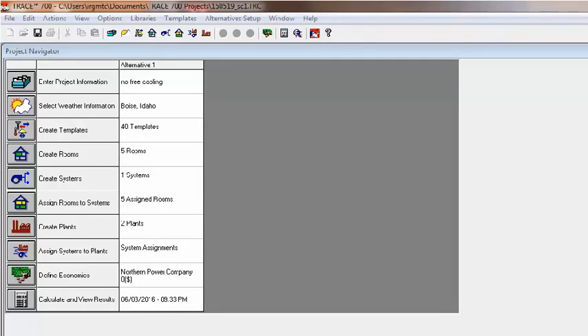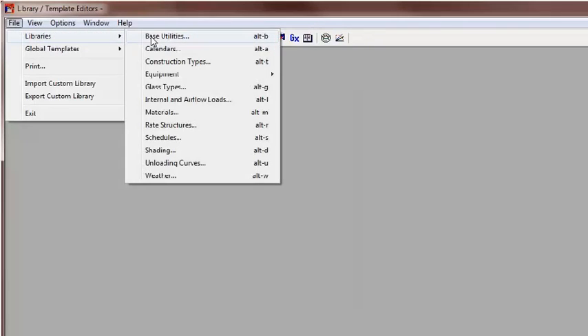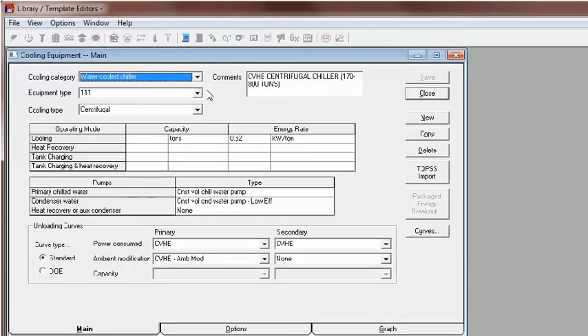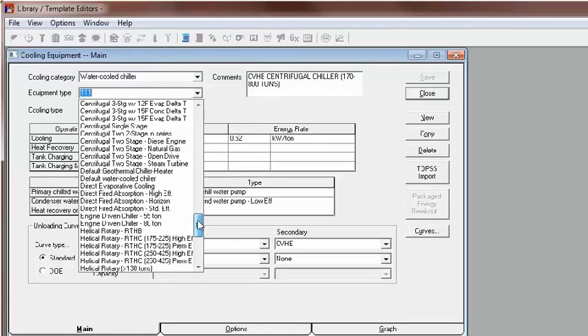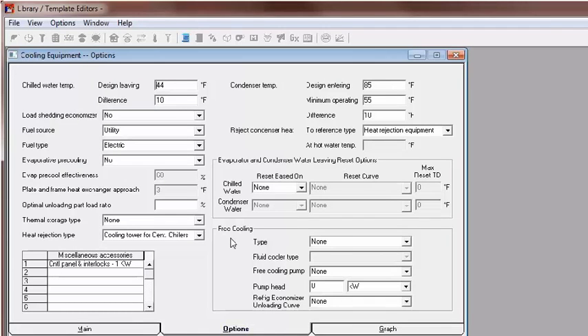I'm going to show you a couple of ways to set up a Waterside Economizer in TRACE 700. You can include free cooling in a custom equipment library member for ease and reuse, or just add it directly to your project alternative if the default heat exchanger works for you. To configure custom equipment, click on the Library Template Editor and select Libraries > Equipment > Cooling. You can only modify custom equipment, so I'll copy the default water-cooled chiller and rename it 'Economizer Demo.' Next, click the Options tab where free cooling type, pump, and full load energy rate can be specified.